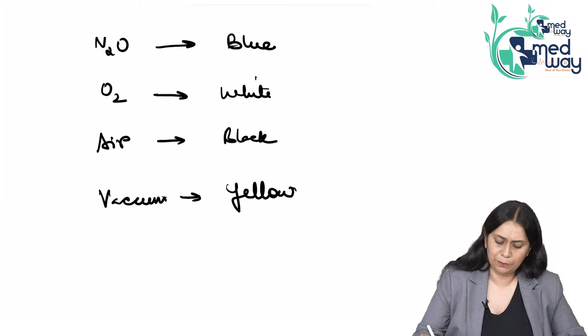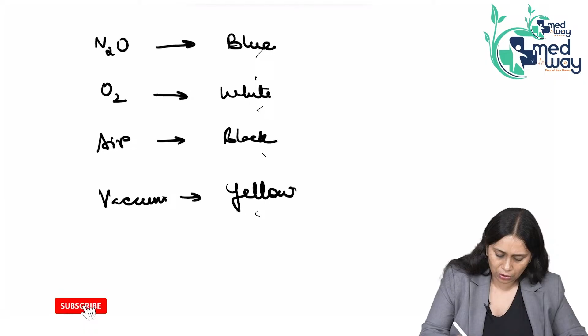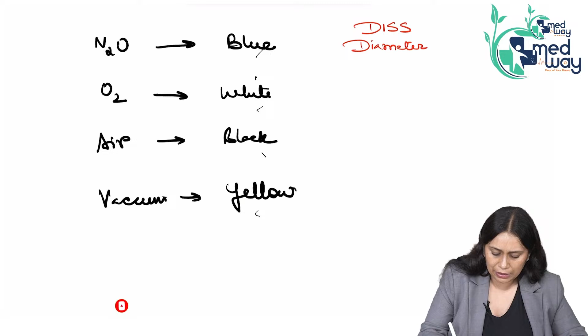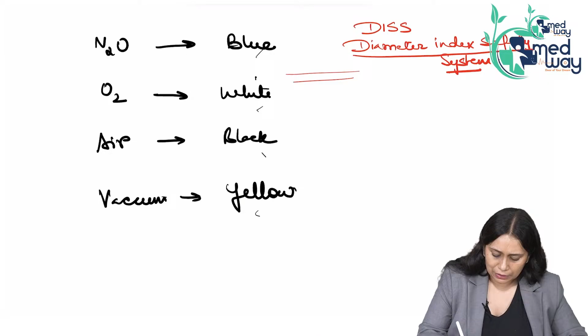And not only color coding is practiced, even the inlets of these pipelines going into the machine have different diameters specific for every gas. So, that is something called DISS, that is diameter index safety system. Every pipeline, the terminal end is specific for that particular gas. So, this system prevents incorrect attachment of pipeline to machine.